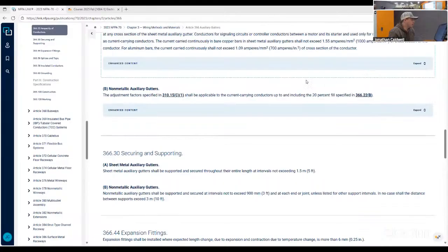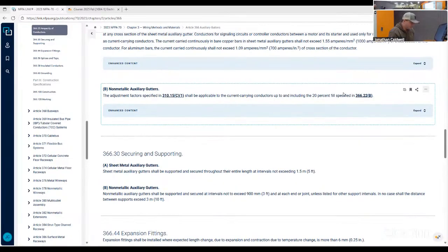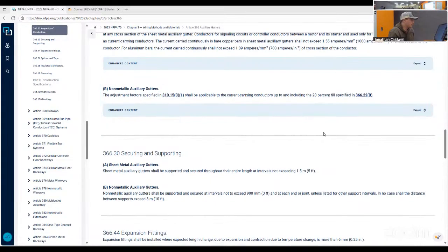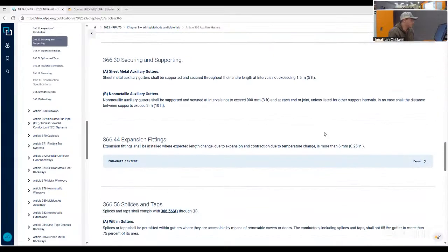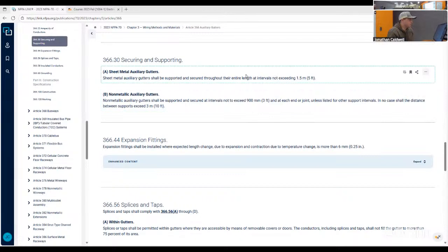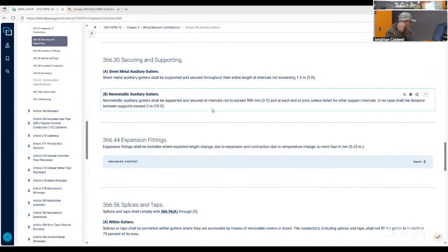The adjustment factors specified apply to current carrying conductors up to 20% fill for non-metallic. Securing and supporting: sheet metal gutters shall be secured throughout their entire length at intervals not exceeding 5 feet, and 3 feet for non-metallic. However, I will say if you have feeders going through your gutter, support it more. Seriously.